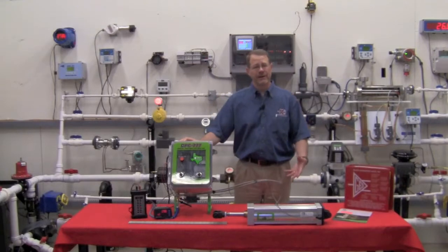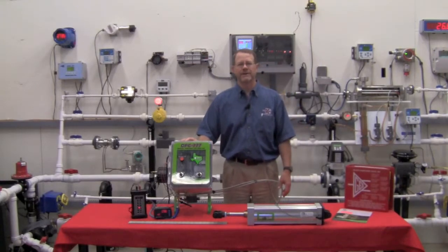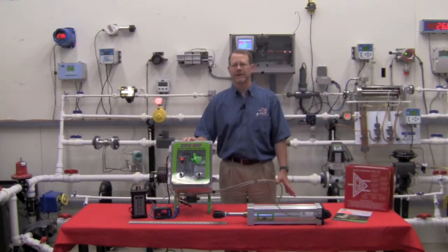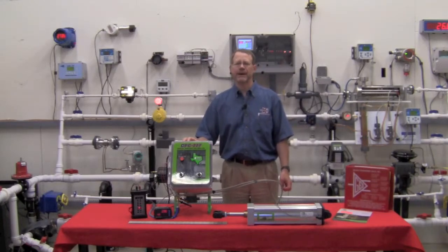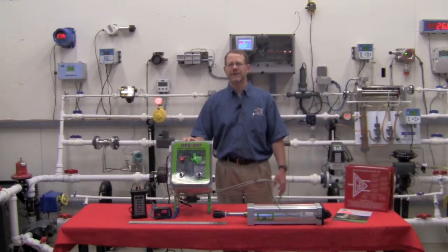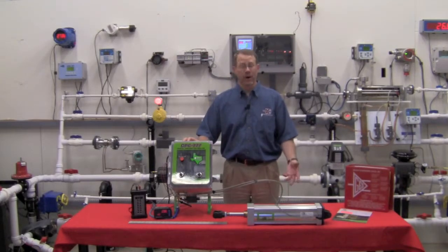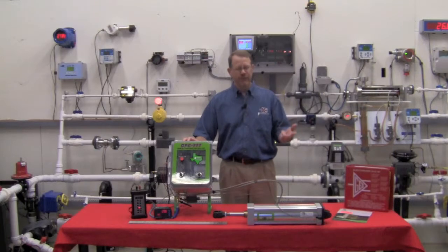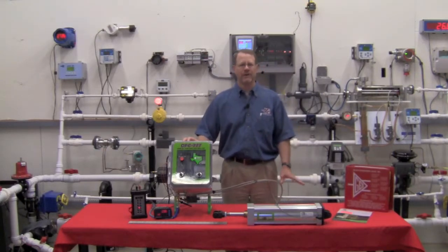As many of you already know, secondary air is introduced at the burner and its flow is determined by a sliding disc or sliding sleeve mechanism that usually is positioned by a linear actuator. Originally, most linear actuators were operated by an electric motor that drives a lead screw type mechanism. In the past, these electrically operated drives were typically placed in one of three positions: light off, full load, and idle or cooling. This was done by setting hard to adjust travel switches. Frequent modulation in the electric drives usually resulted in premature failure due to limited duty cycle design.